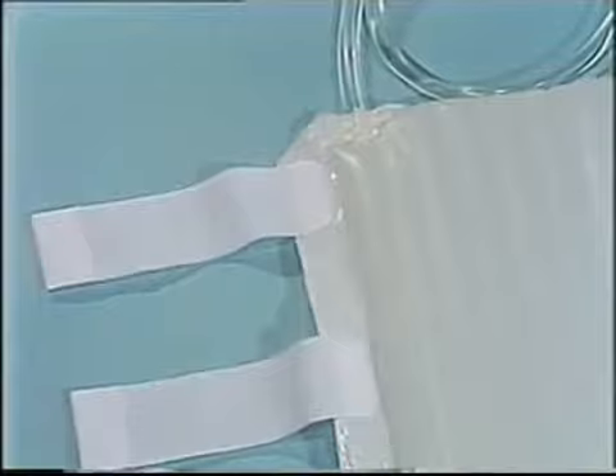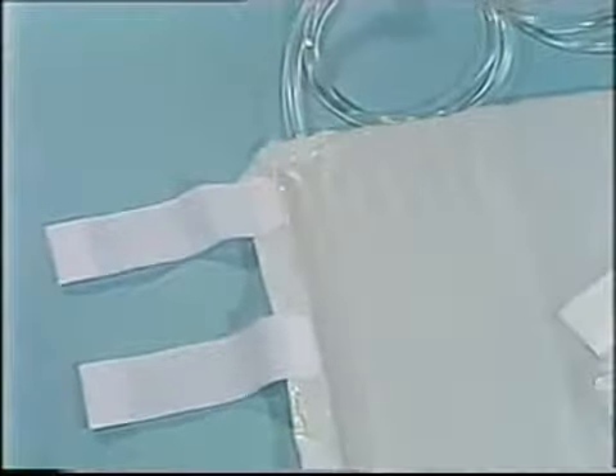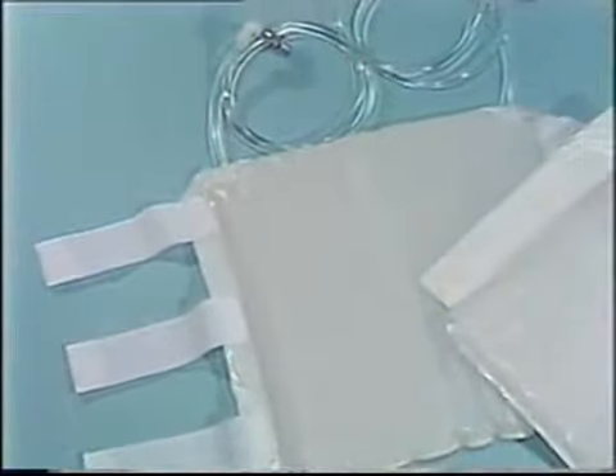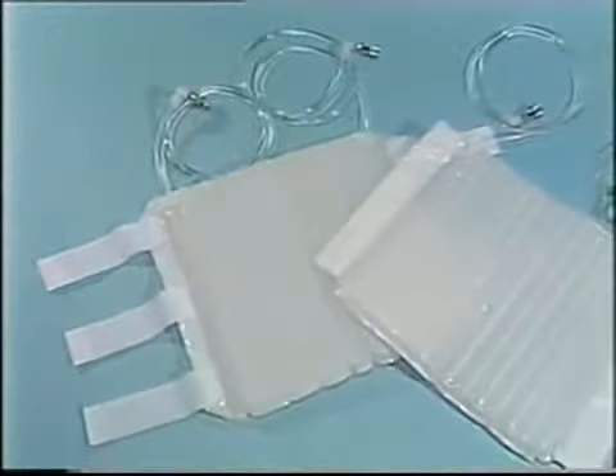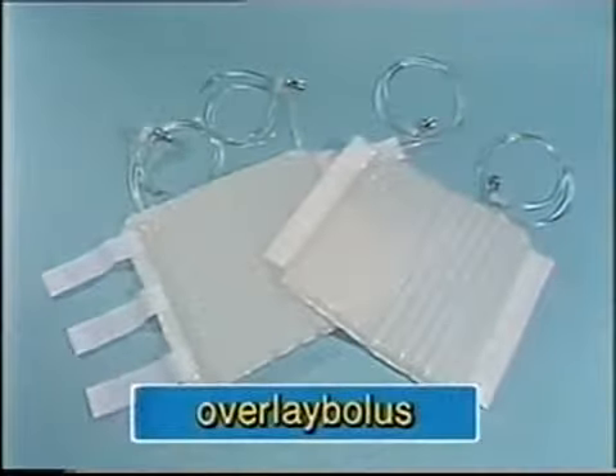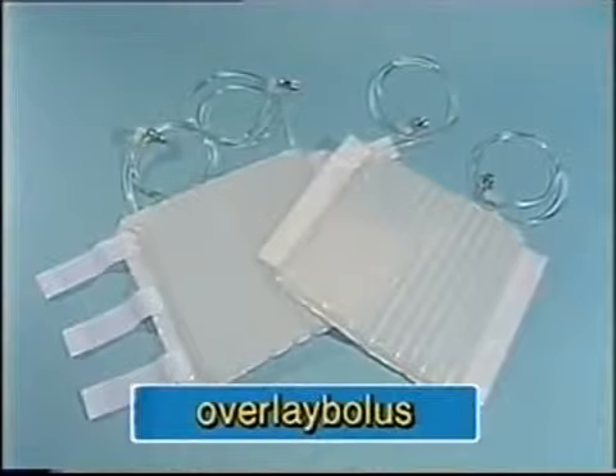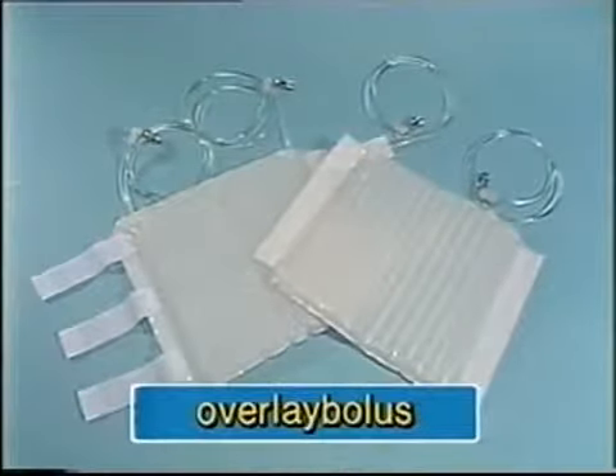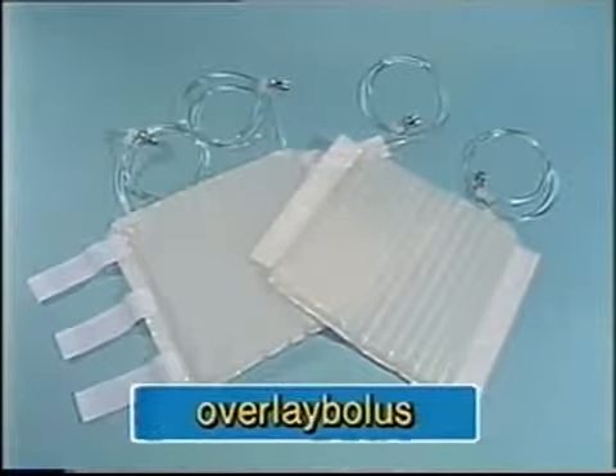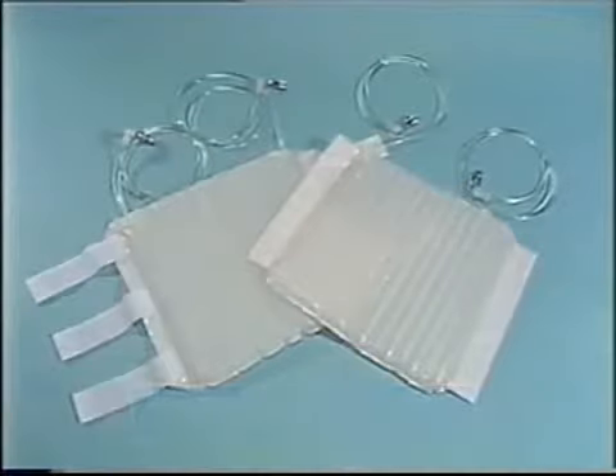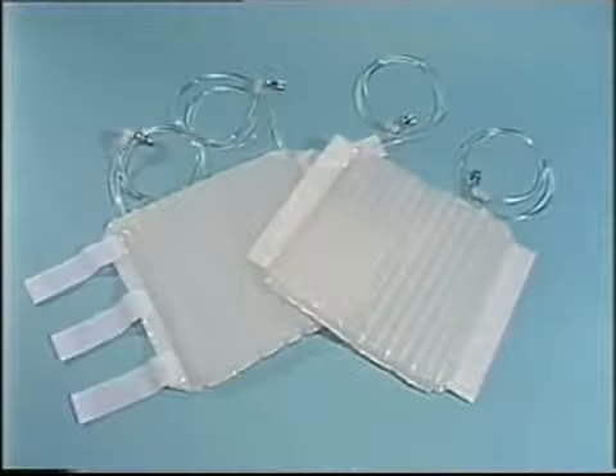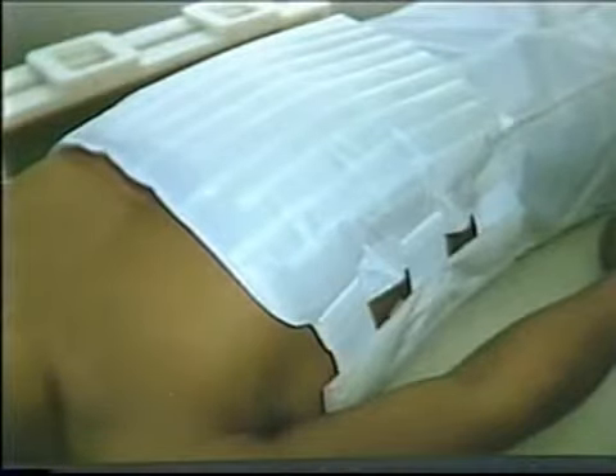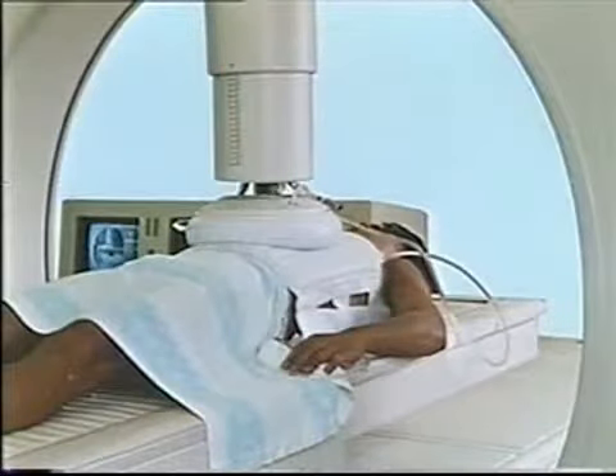Recently, a device was developed to lower the high temperatures generated around an electrode, or in the area in contact with an electrode pad. This device is called an overlay bolus. It is a flexible polyurethane bag containing salt water with a temperature that can vary from 3 to 40 degrees centigrade and which circulates freely. The overlay bolus evenly distributes the effects of the lines of electric force, and the high temperature produced in a localized area on the surface above the heated area is greatly lowered.